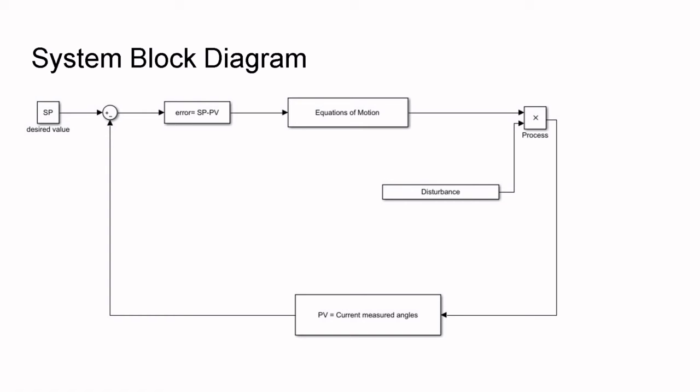Only the proportional control is utilized, hence P-only. The motor current is set in proportion to the existing error. The integral and derivative components are not utilized, and so to correct for error accumulation and prediction, manual input is required. This is accomplished with the trim function on the transmitter.